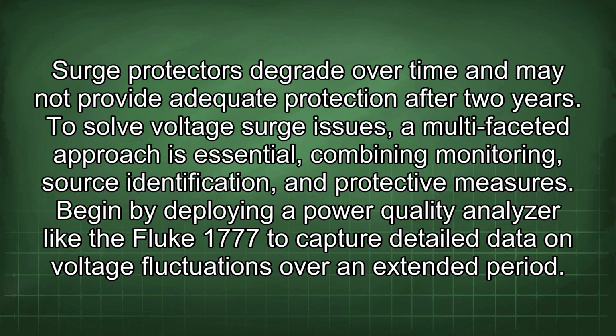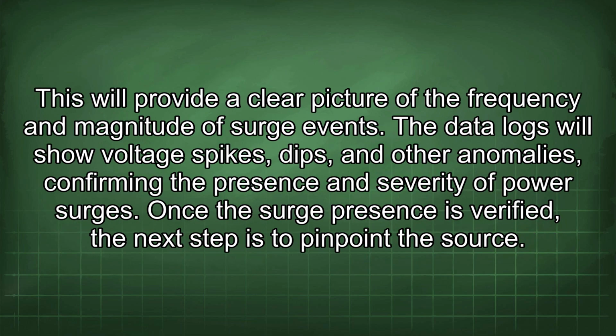To solve voltage surge issues, a multifaceted approach is essential, combining monitoring, source identification, and protective measures. Begin by deploying a power quality analyzer like the Fluke 1777 to capture detailed data on voltage fluctuations over an extended period. This will provide a clear picture of the frequency and magnitude of surge events. The data logs will show voltage spikes, dips, and other anomalies, confirming the presence and severity of power surges.